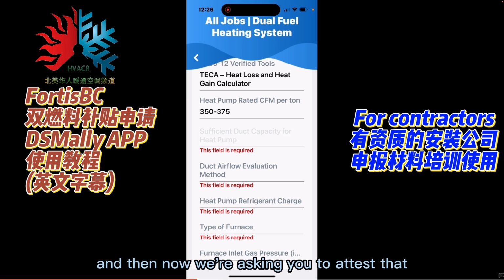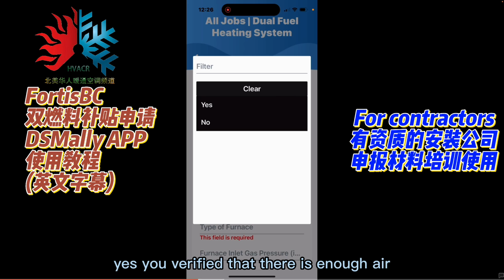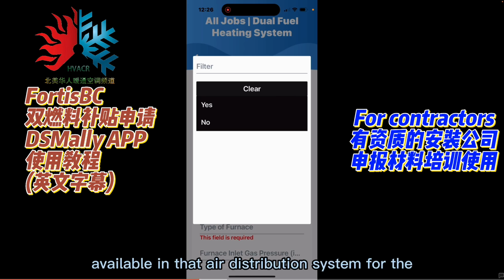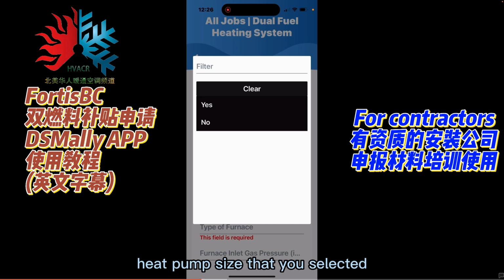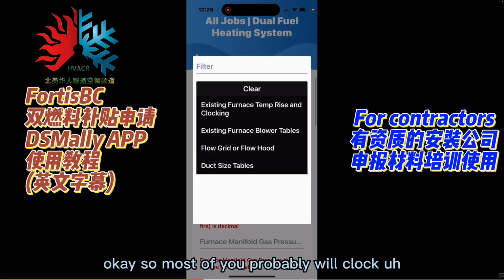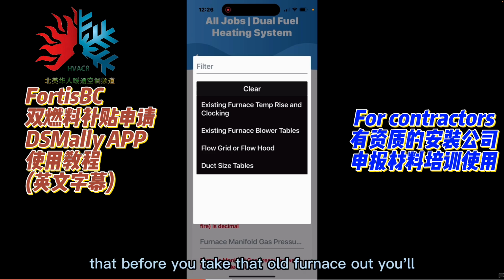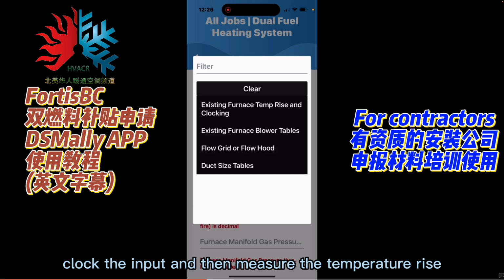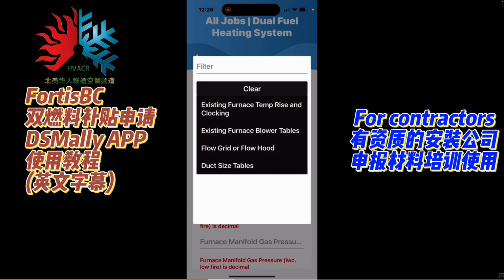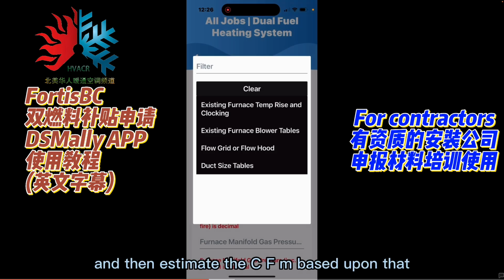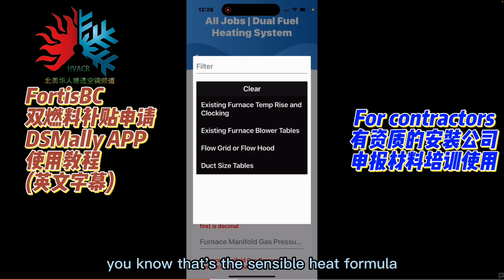And then we're asking you to attest that, yes, you verified that there is enough air available in that air distribution system for the heat pump size that you selected, and then how you did that, okay? So most of you will probably clock the input before you take that old furnace out, then measure the temperature rise and estimate the CFM based upon that. That's the sensible heat formula.